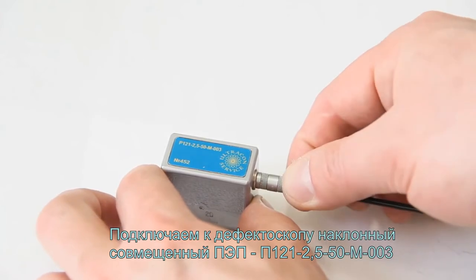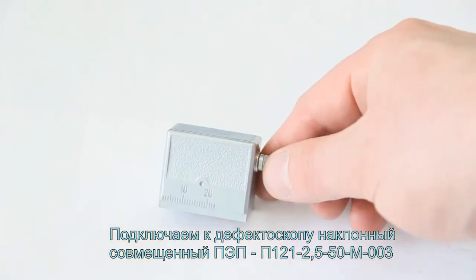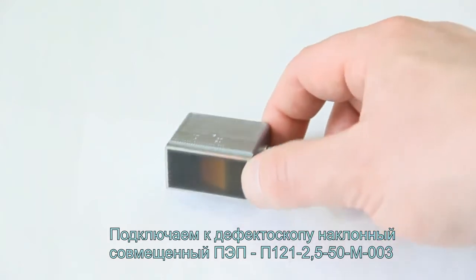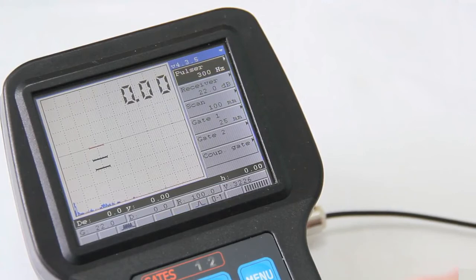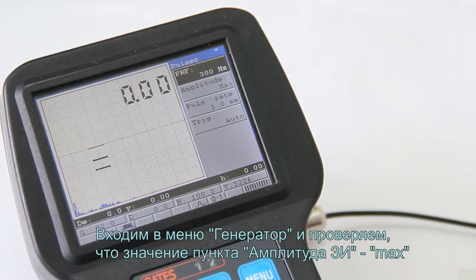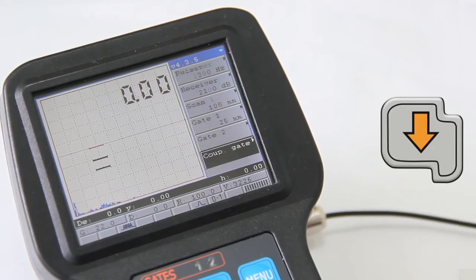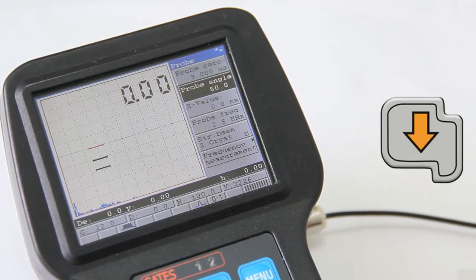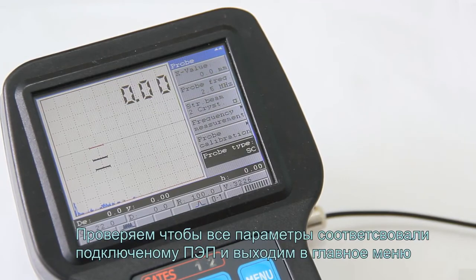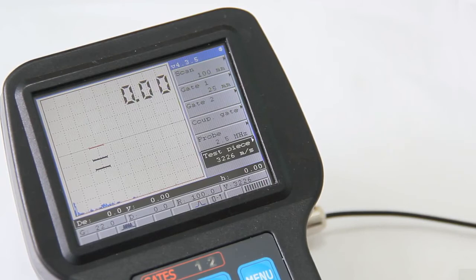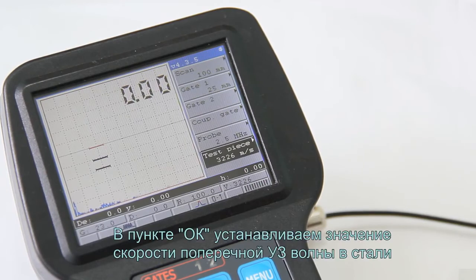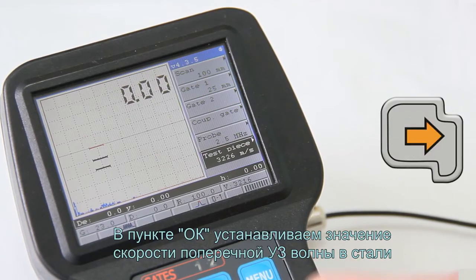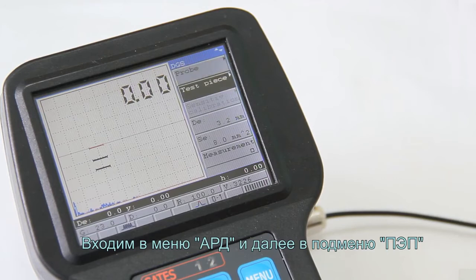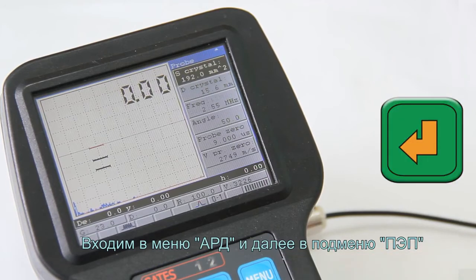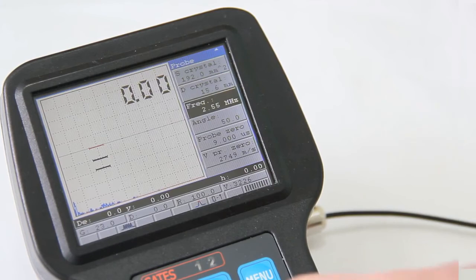Connect the angle beam single crystal probe to the Flaw detector. Enter the pulser menu and check the amplitude item to be set to maximum. Return to the main menu. Enter the probe menu. Check that all parameters correspond to the connected probe and exit to the main menu. In test piece item, set the transverse velocity in steel. Enter the DGS menu and then the probe submenu, where set the true value for the probe frequency and check the correspondence of other parameters.